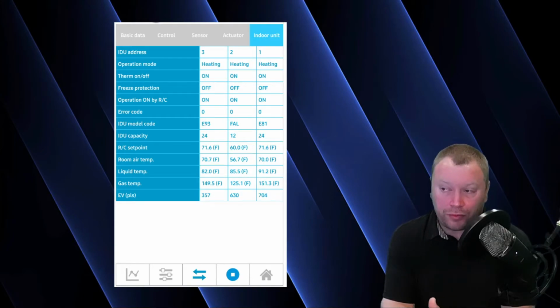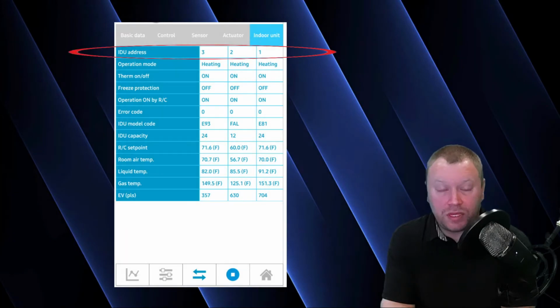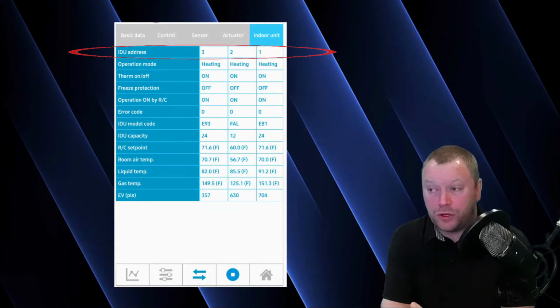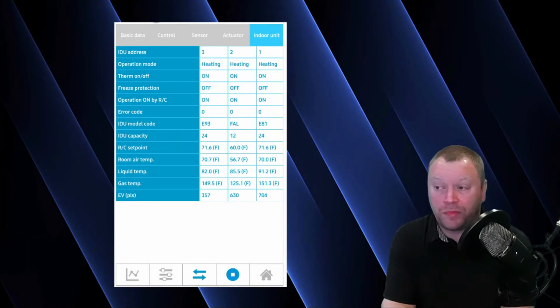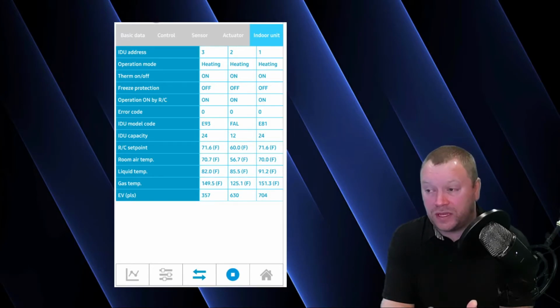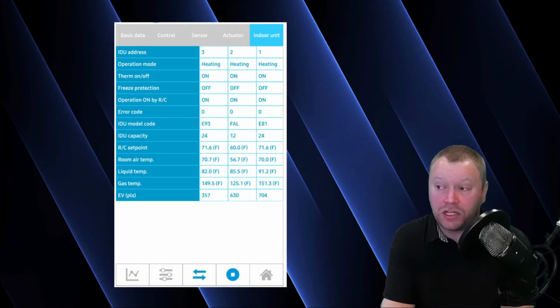So when we look at our 3 indoor units, unit number 3, unit number 2, unit number 1. Unit number 3 and unit number 1, those are my 2-ton units. One of them is my gas furnace. One of them is my air handler. We don't know just by looking at this information which one is which though. Really, the only way to know which one is which is by going in and turning one off or giving one of your units a different set point than the other so that you can distinguish which one is which when you have 2 units or more of the same size.